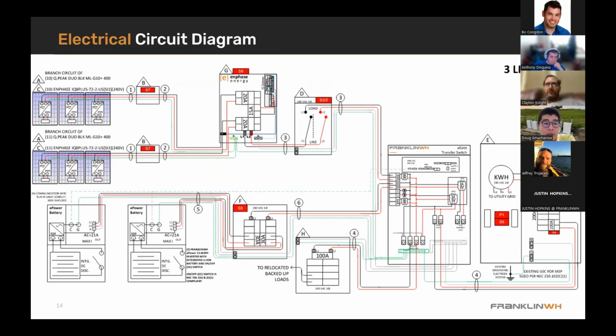Here is an example of a 100 amp service with a nice big 8 kW PV system and 2 batteries on there. To give you a sense of what you'd need in terms of balance of system and costing, you have your specialized 100 amp breaker here, which flows into your aGate. The additional optional modules shown here are the smart circuits and generator modules.